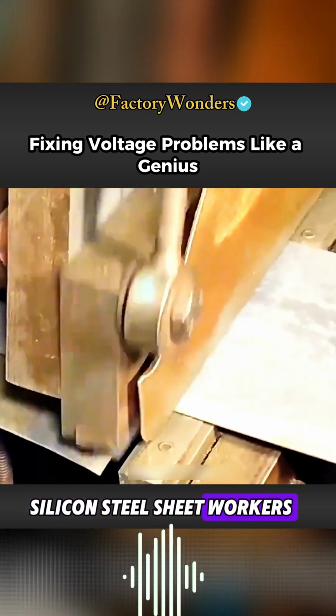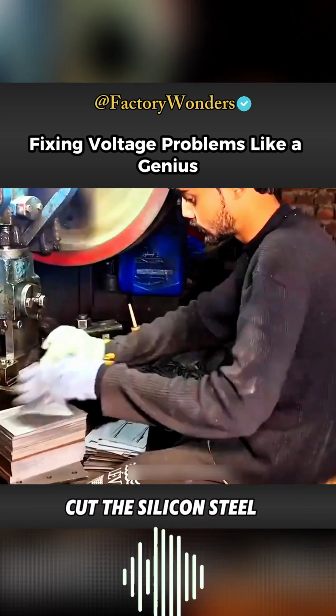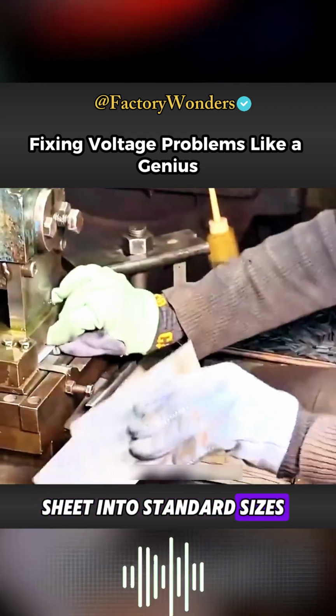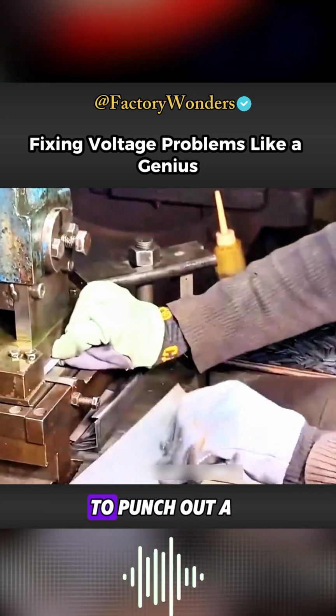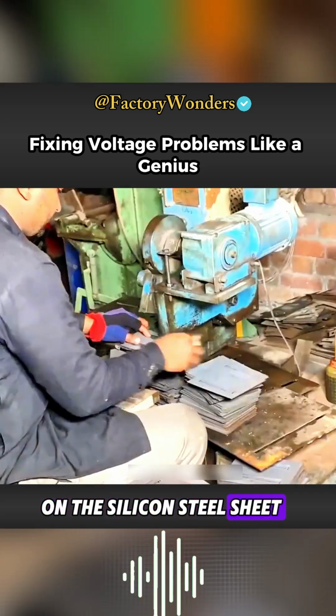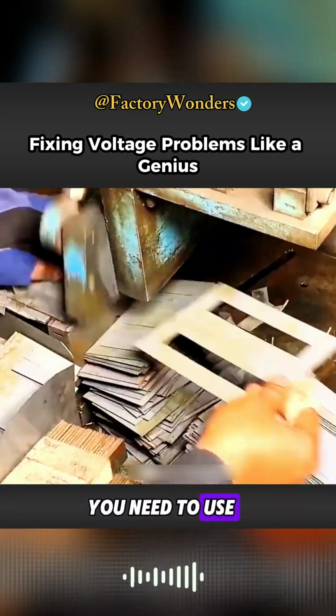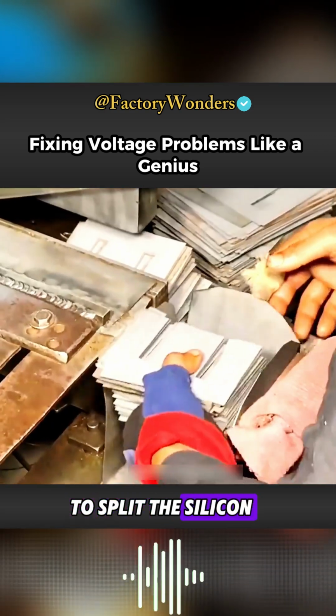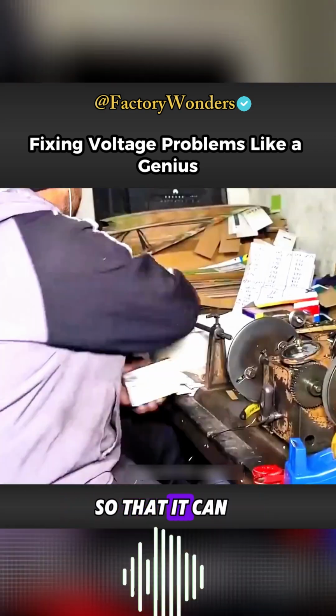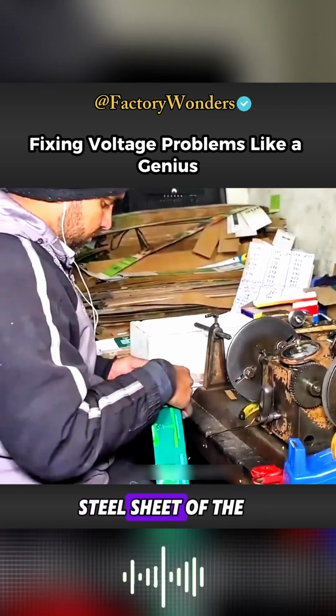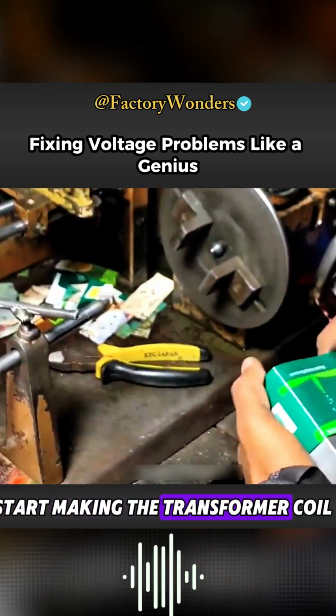Silicon steel sheet workers will use a shearing machine to cut the silicon steel sheet into standard sizes and then put it into a punching machine to punch out a suitable shape on the silicon steel sheet through a punching die. Next, you need to use a shearing machine to split the silicon steel sheet into two so that it can be quickly made into a silicon steel sheet of the same type. Then you need to start making the transformer coil.